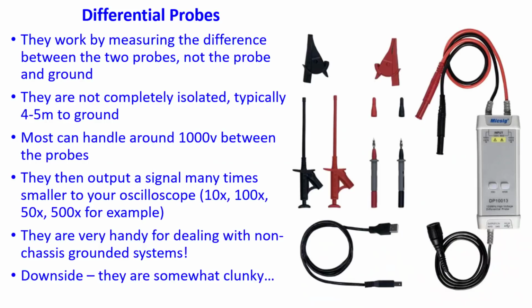Very different setup here. So then what gets sent out of this, there's some circuitry in here. What gets sent out of this is then a much smaller signal feeding back to this that is not referenced back to this right here. In other words, this probe that's ground here is not directly tied to this. There's usually 4 or 5 megaohms between these two here. So not totally isolated, but for all intents and purposes, pretty darn close.